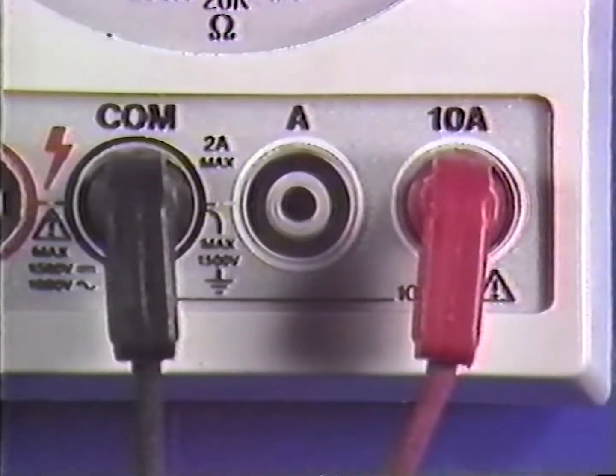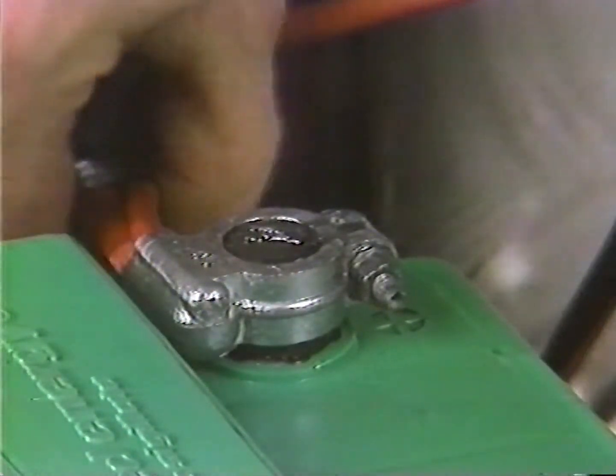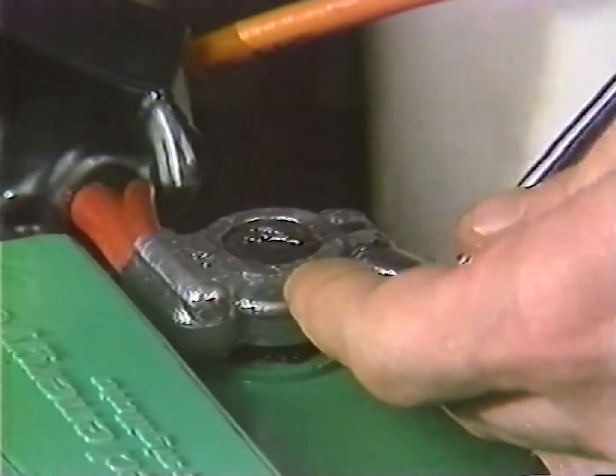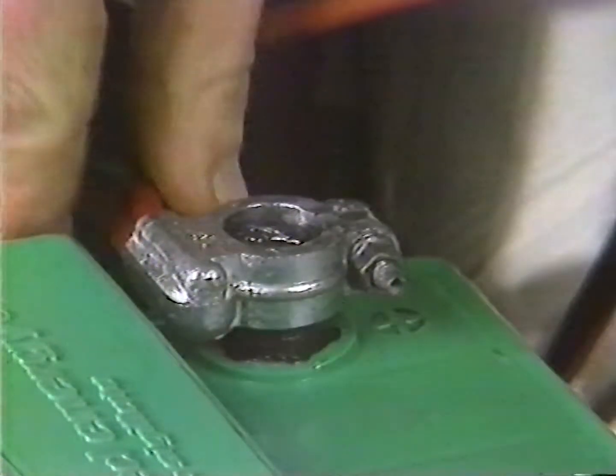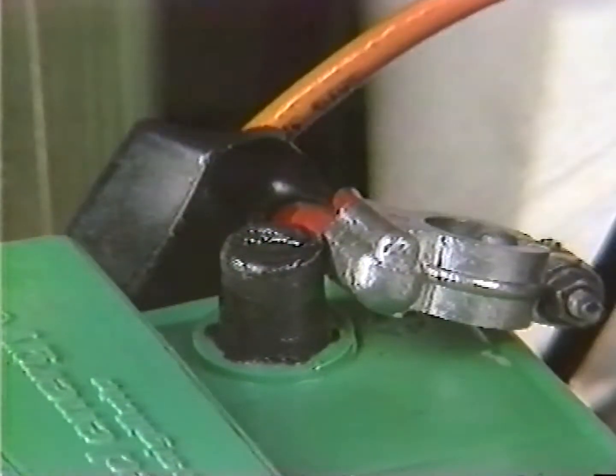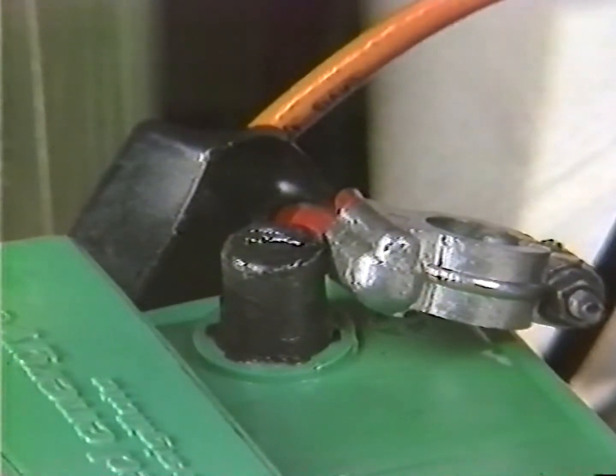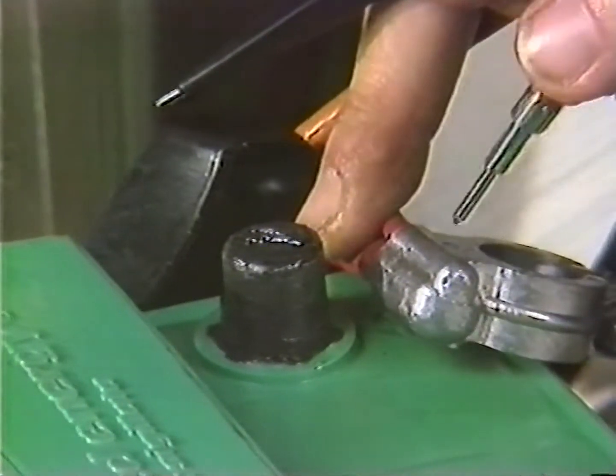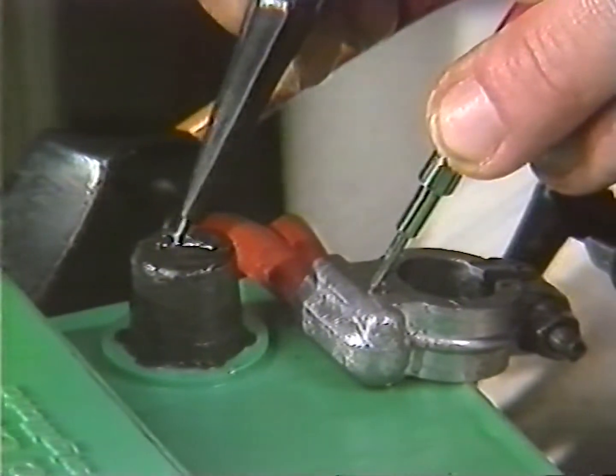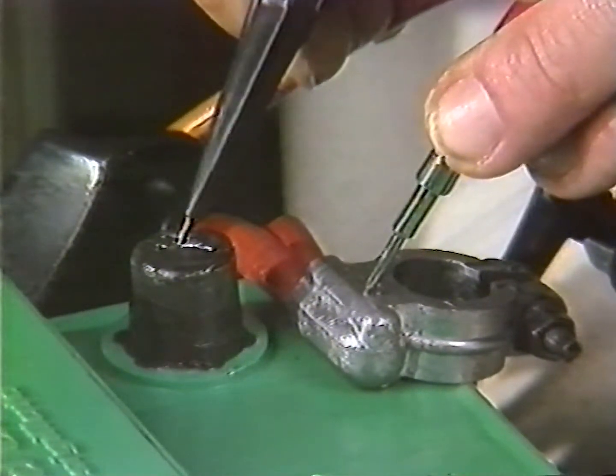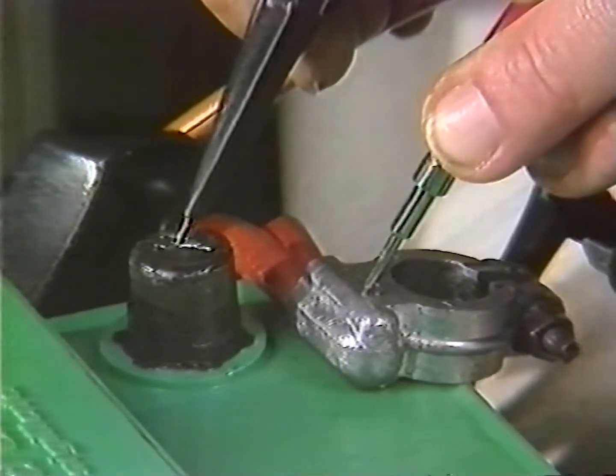To check on the level of current leakage, we use a multimeter as an ammeter, connecting the plug to A. As you know, the instrument for measuring current intensity has to be connected in series with the circuit, with its black probe connected to the positive pole of the battery and its red probe to the terminal which has to be disconnected from the positive pole of the battery itself.